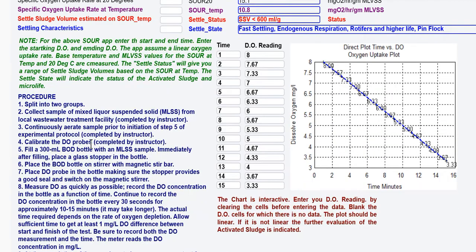The chart is interactive. You enter your data from your test here — this is based on 15 minutes, which is normally a standard time. If you were only to run 10 minutes, you would have to blank out the values from 11 to 15. This chart gives you an idea of whether or not consumption is linear. If it wasn't linear, you would have to look at your biological community and how it's reacting.